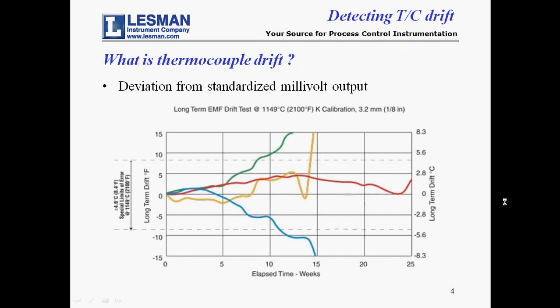Thermocouple drift is the deviation of a thermocouple's output signal from the published values in the standard reference tables. The chart shows a test of several different thermocouples at a constant elevated temperature over time. The center line is zero deviation from the constant temperature. The dashed lines above and below the center are the standard limits of error. You can see the green, blue, and yellow curves drifting and wandering away from the zero deviation center line over time. The temperature signals from a drifting thermocouple are not true temperature measurements — they are false temperature measurements.